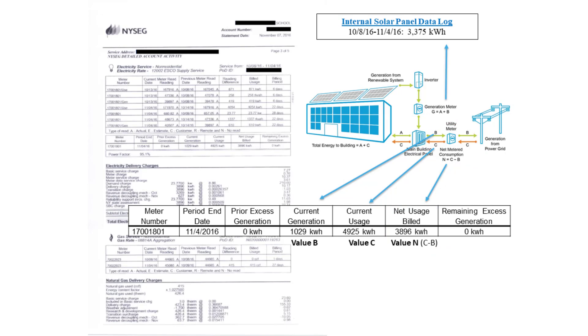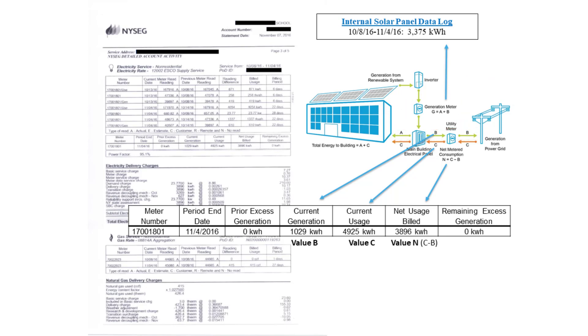In addition, because this property has an on-site generation meter, we can calculate the total amount of energy generated on-site during the utility billing period, value G. This value minus the amount exported to the grid, Flow B, or current generation in this case, is equivalent to Flow A, the amount of energy generated on-site and used on-site. This value doesn't show up on the utility bill, but we will need to know it when it comes time to enter data into Portfolio Manager.